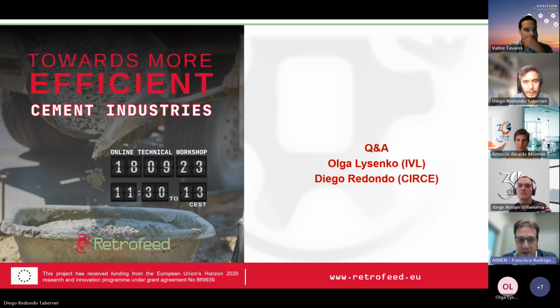Well, what should be clear is that with the spectrophotometry solution, what we intend to do is not to make a precise determination of the chemical phases, because the reference system that is used right now is the diffractometry system, which is the best one. This is clear, and this has been established for a long time in the cement industry.